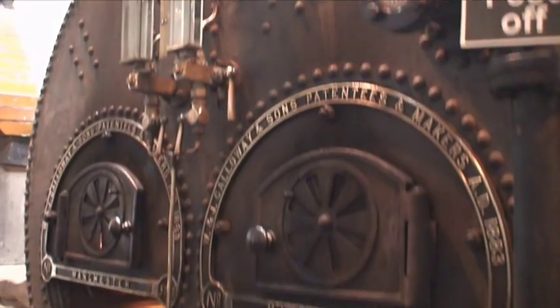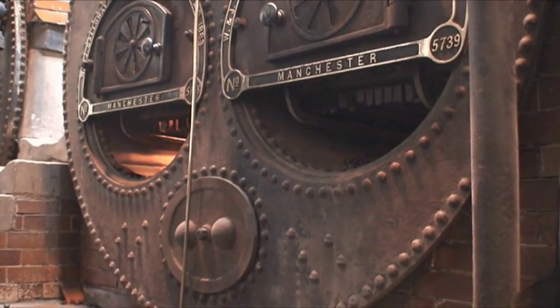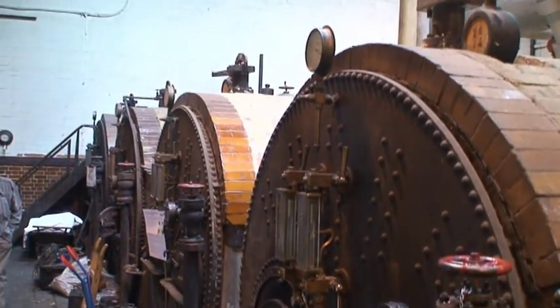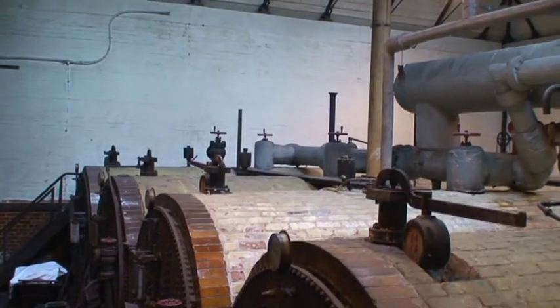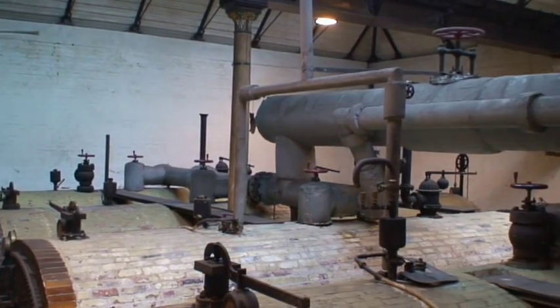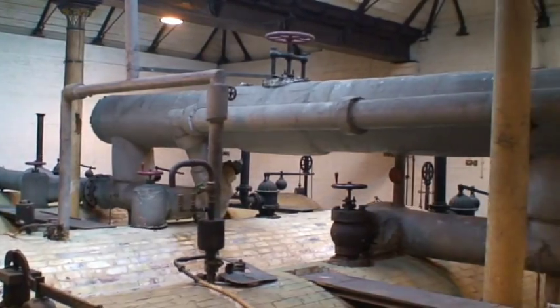We're now in the boiler house at Papplewick Pumping Station, in front of six Galloway boilers. These are probably the oldest boilers in the world that are still insured for steaming. The boilers are made by Galloways and Sons of Manchester. They are a Lancashire type — they've got two furnaces but they're not true Lancashire boilers; they actually have Galloway tubes in them. They used to use three for three months and then swap over to the other three, while the finished set was cleaned out and got ready for next use.